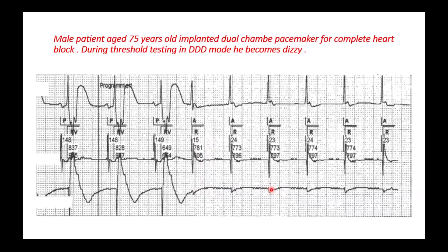the atrial pacing. Interrogation during testing is very important. In some machines, you have to choose dual EGM so that you can see the atrial EGM, the gray one, and the ventricular EGM, the one under. In the ventricular EGM you can see the spike, appreciate the first 3 beats: spike and QRS complex, spike, QRS complex, spike, QRS complex, and then nothing. What is this nothing? There is a far field atrial spike, the small one in the ventricular chamber, which gives a wrong value, as if this is ventricular activity. This is why crosstalk is dangerous, because one chamber can give false orders to the other chamber that there is activity, and this makes the patient go into syncope, maybe arrested.